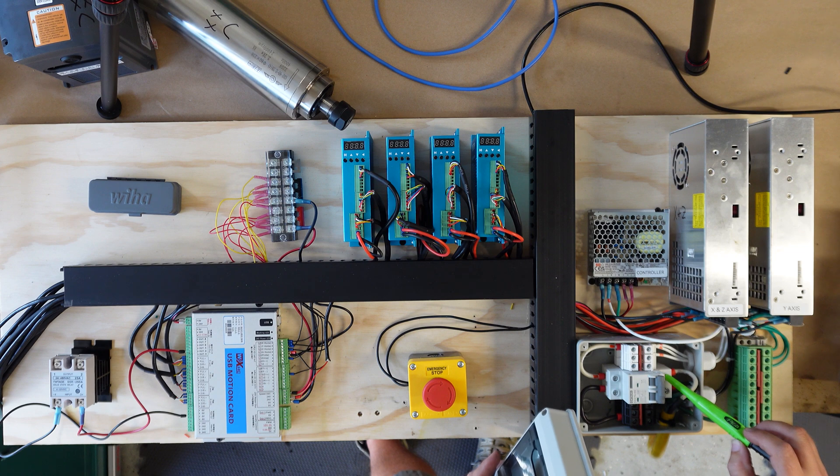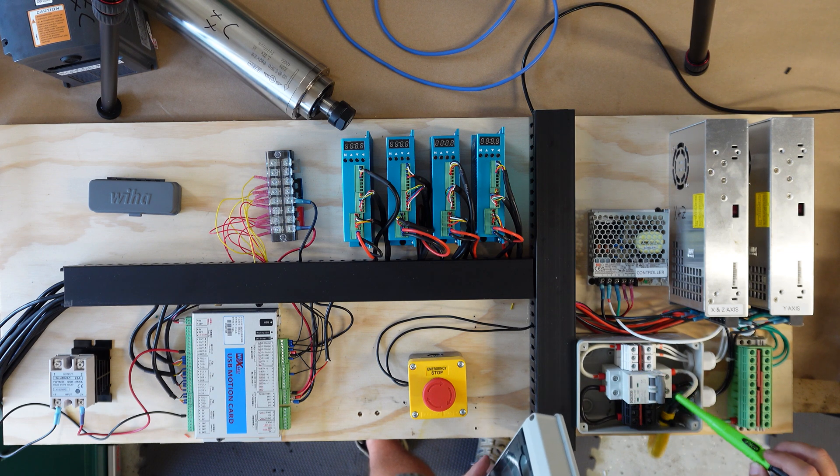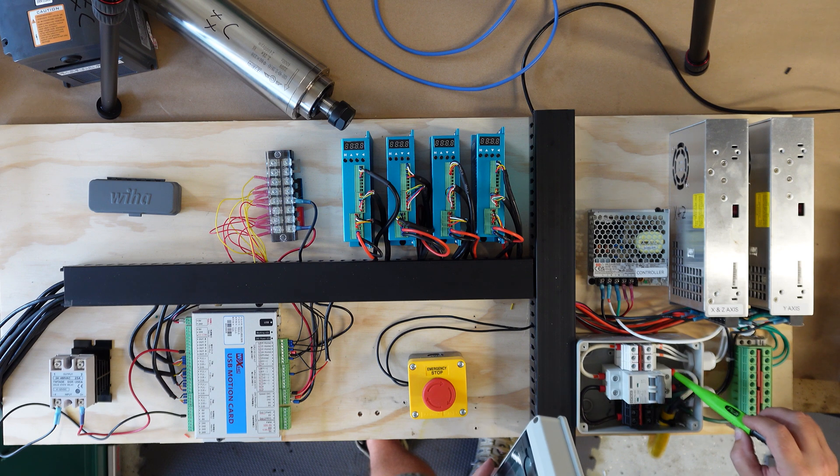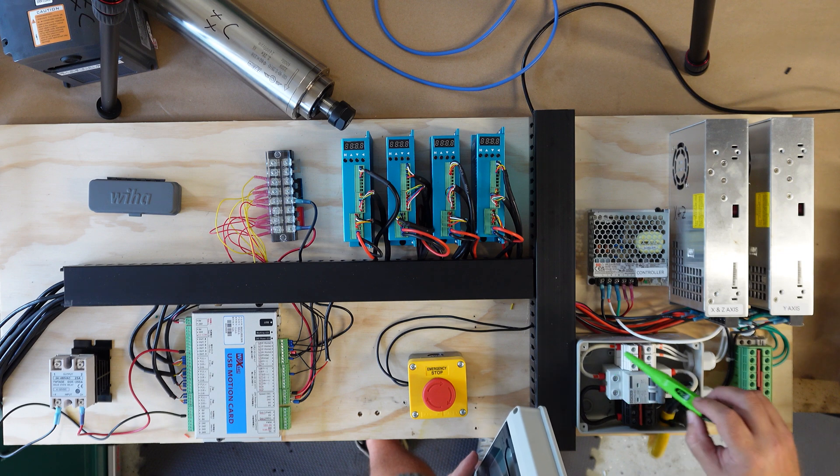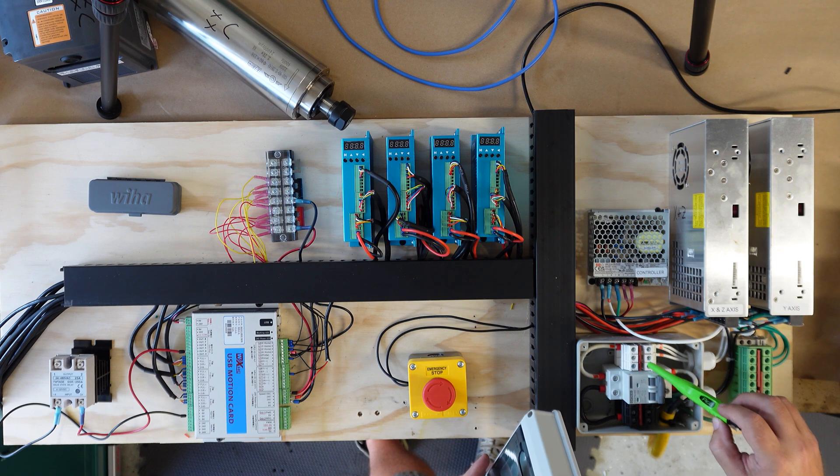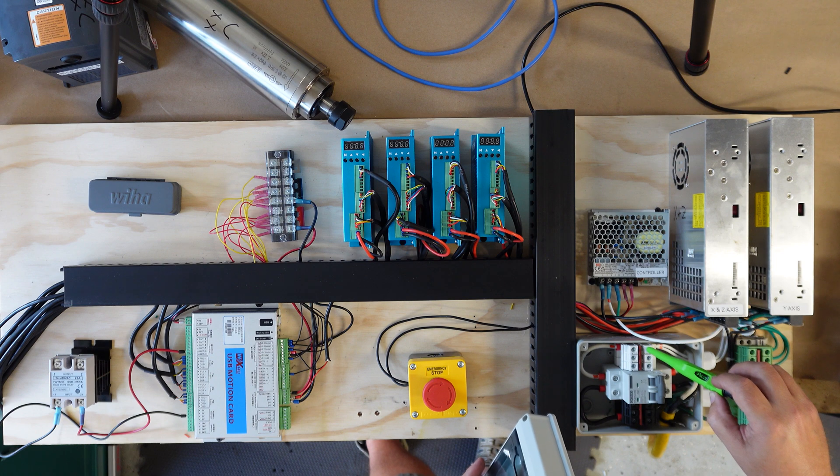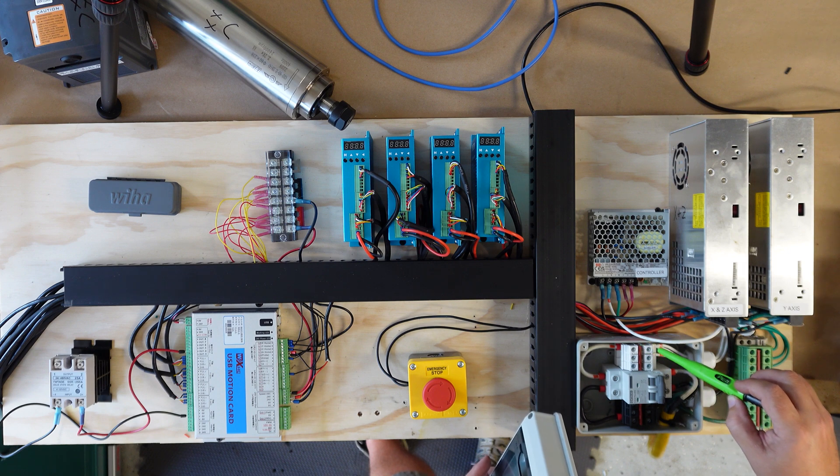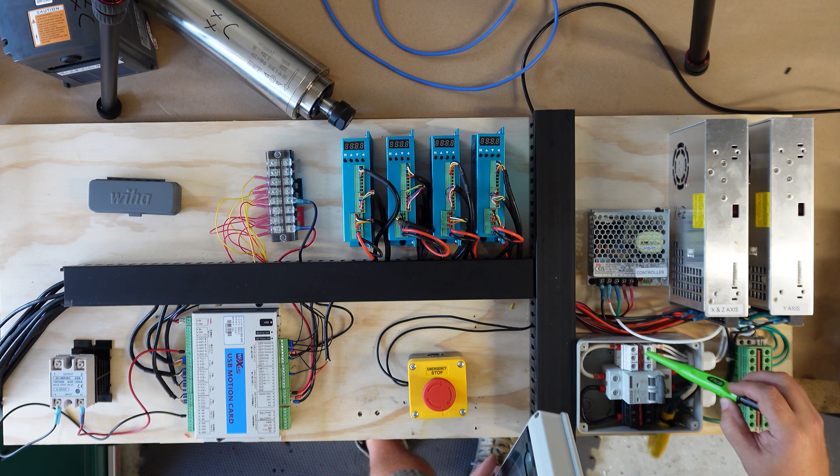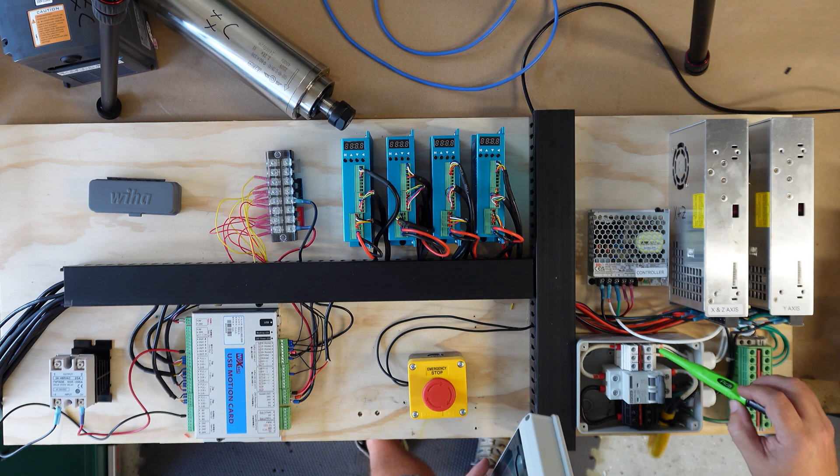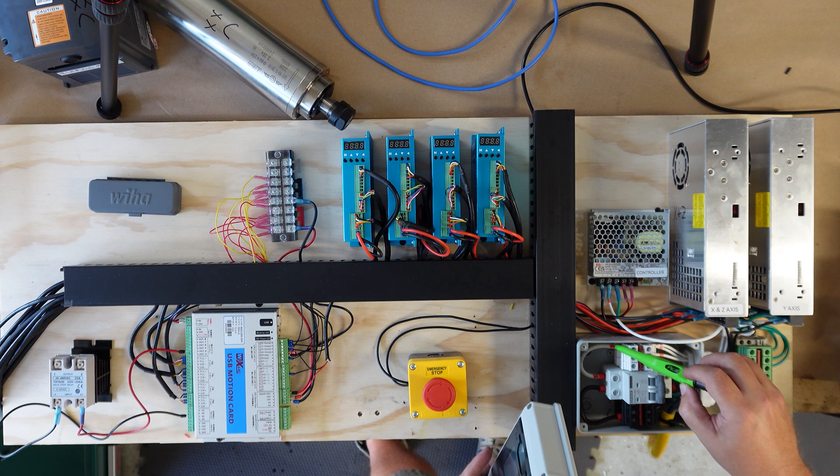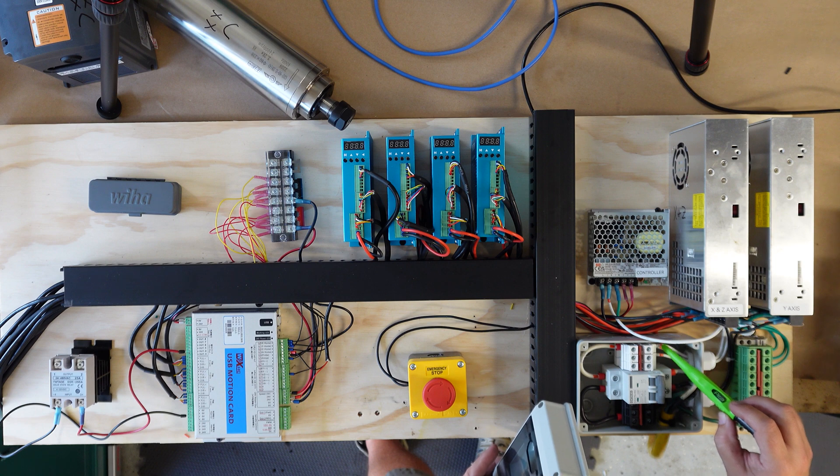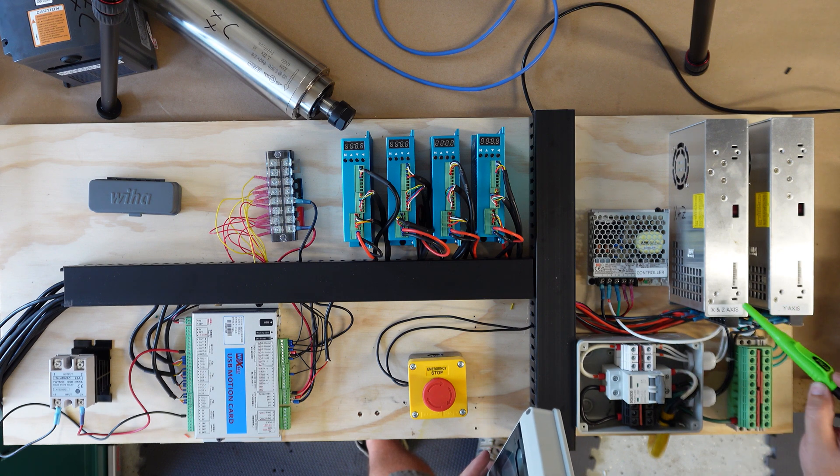Again, this particular cable I'm using has a black, white, and a ground. So I am keeping those colors, but I've marked everything red. I'm actually going to get some red electrical tape to make that a little bit more permanent. So I have incoming power here. It's going into, this is a 30 amp circuit breaker mounted on a DIN rail. So I have white or supposedly red going into this side. Coming back out to a terminal block where I've got three options, three terminals here.